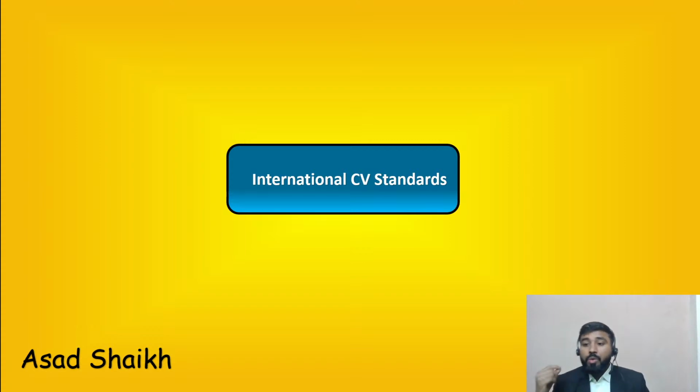A lot of your points are related to sizing. I think we should definitely cover a separate session in depth on sizing. The reason is, when it gets to the velocities which you said, when to take stellited trim, this gets a bit deep when you do sizing. Without that, it is a little bit difficult for us to answer. A lot of people assume that when you've done stellited, it is good enough. But personally, no, it depends on how much is the DP that you are having. So that would be this thing.